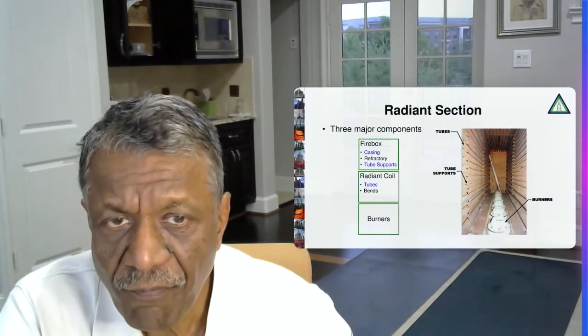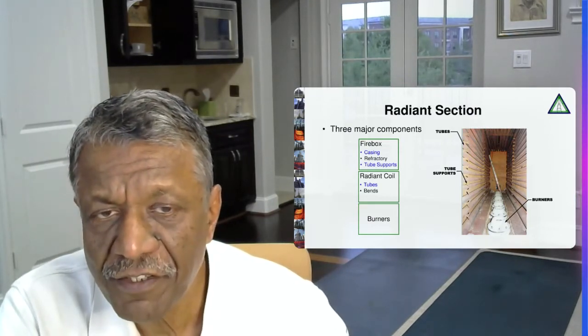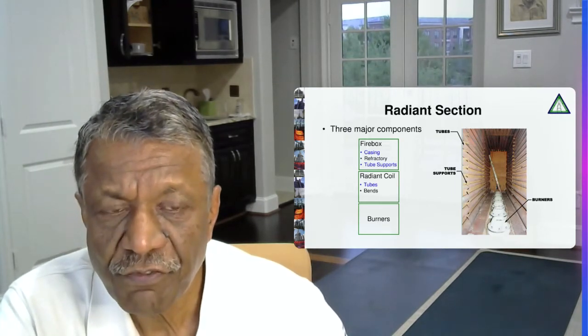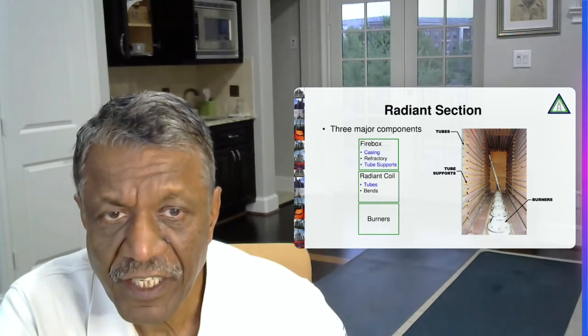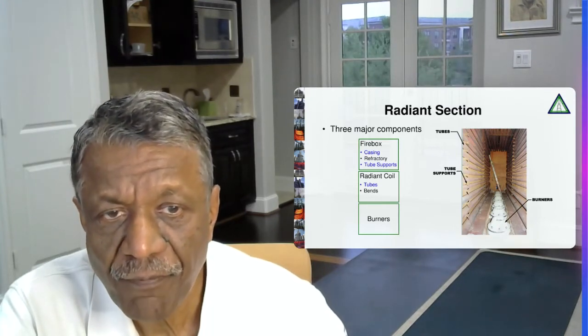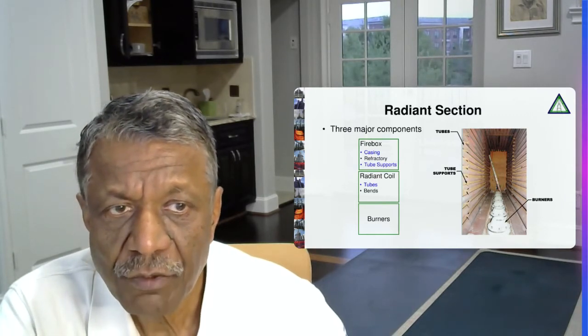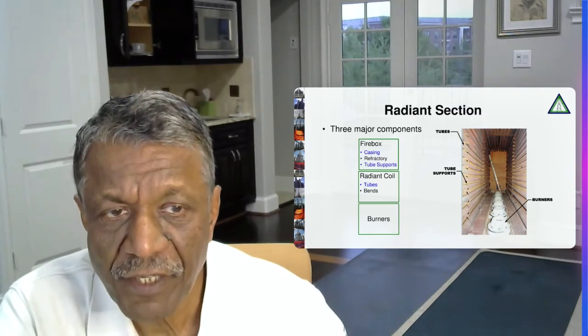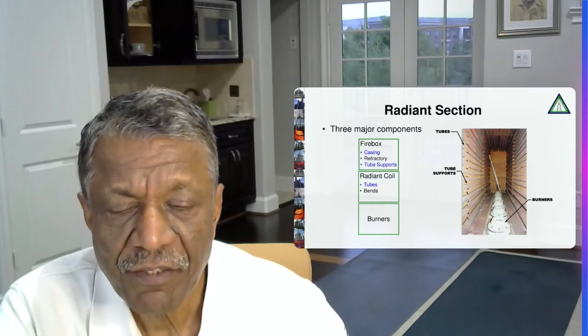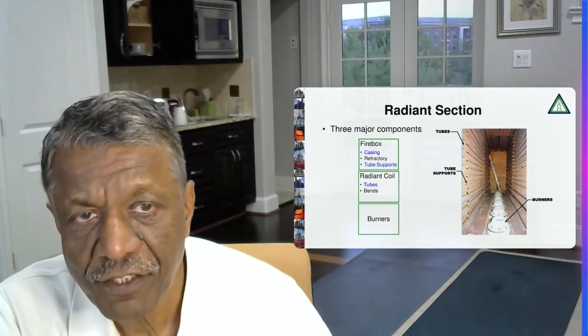When we talk about radiant section, again we can break it up into three sections. We can break up into firebox. Firebox consists of steel casing on the outside, refractory lining which is used for containing the heat losses, minimizing, containing the heat and minimizing the heat losses. And tube supports are used for holding the tubes. And then we have the radiant coil in which the fluid is flowing throughout the radiant section and absorbing heat. And burners located on the floor of the fired heater which are providing the heat to the fluid. So these are the three major components of radiant section.